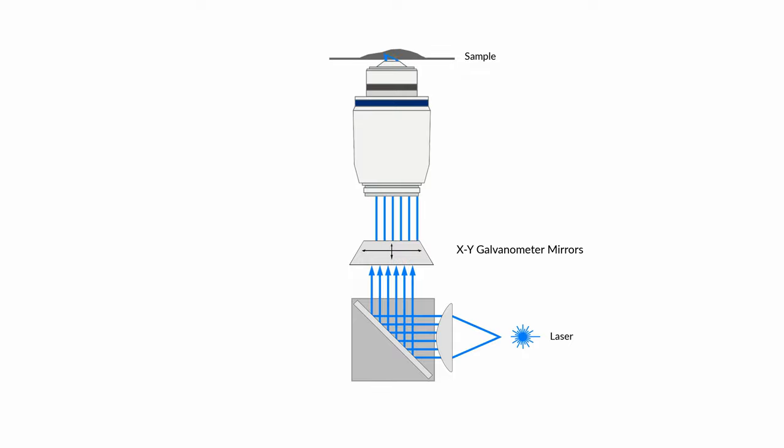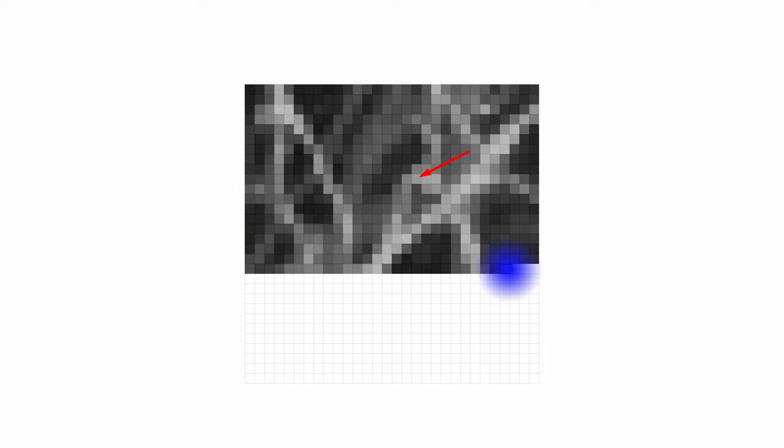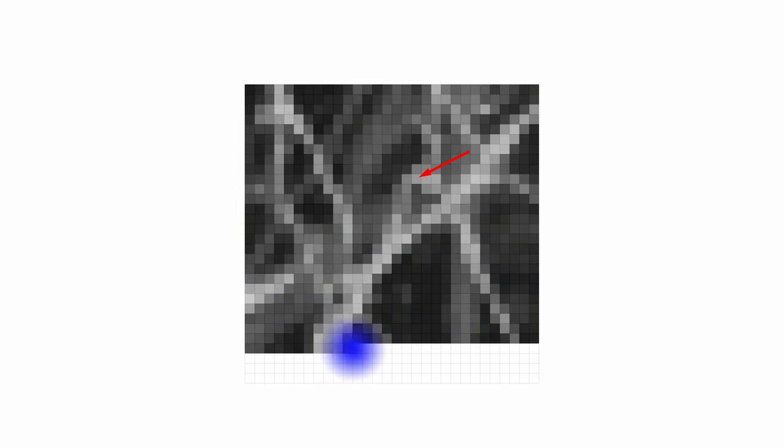So while the scan is progressing, areas that are not currently being sampled will not be illuminated. The emission signal collected by the objective will pass through the scanners from the opposite direction on its way to the pinhole and detector. As the emission signal exits the scanners, it becomes stationary, referred to as descanned, which makes it easier to align the emission and pinhole optics in the optical path. As the illumination laser passes over each region, a detector records the amount of fluorescence emission light at each location and then maps that signal as an intensity value to a pixel located in the corresponding region of our final image.